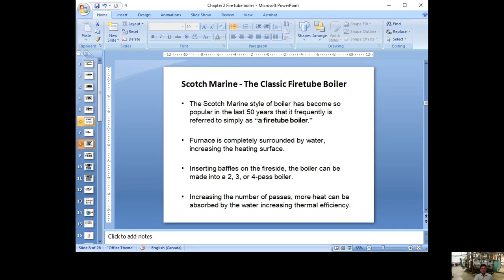They insert baffles on the fire side to redirect the fire and create two, three, or four passes. The more passes you have, the more chances to absorb the heat before it goes up the stack, so thermal efficiency is much better. Because of the simple construction and good enough efficiency, this type of boiler has stayed in use for a long time.